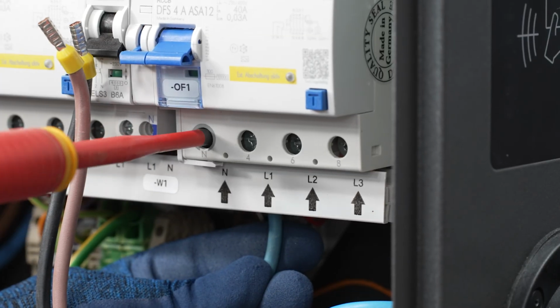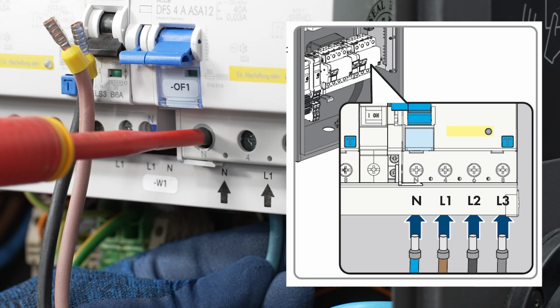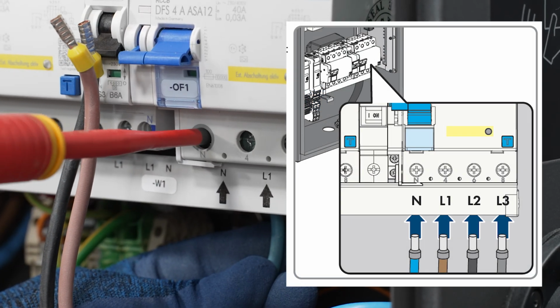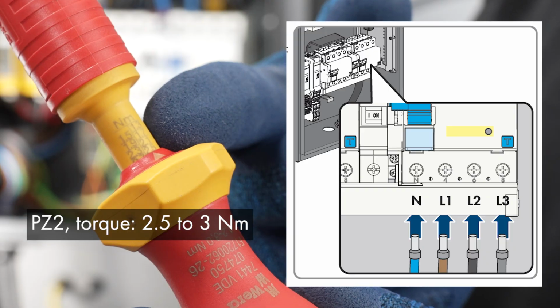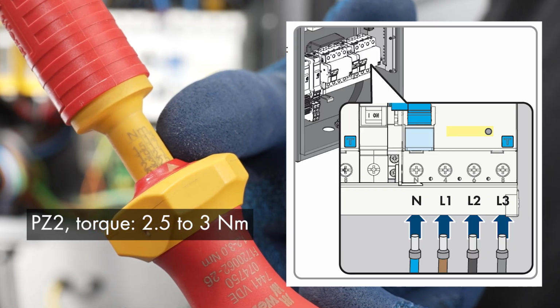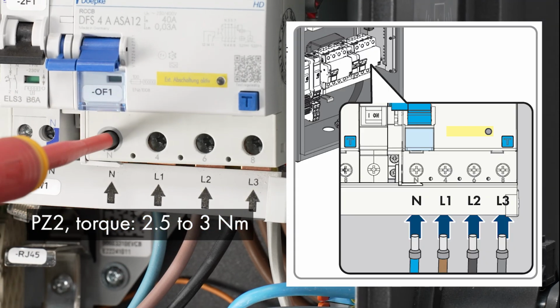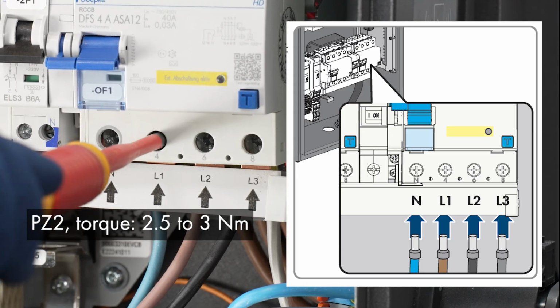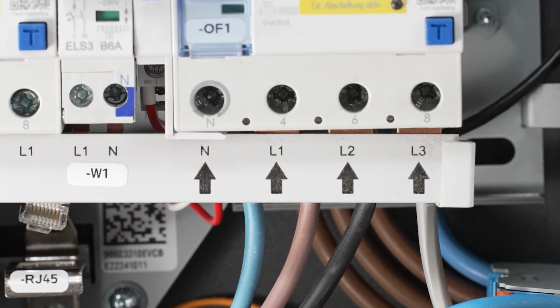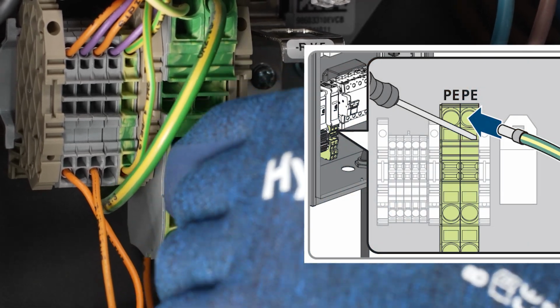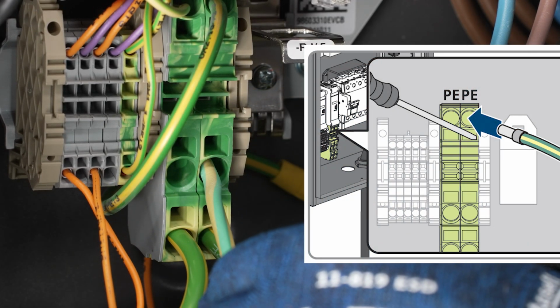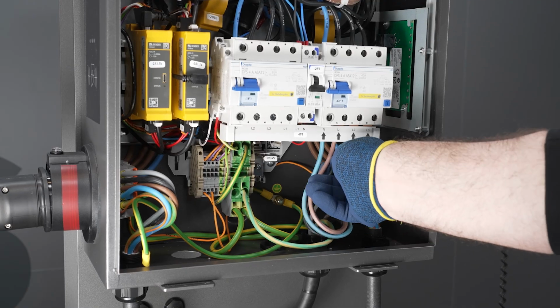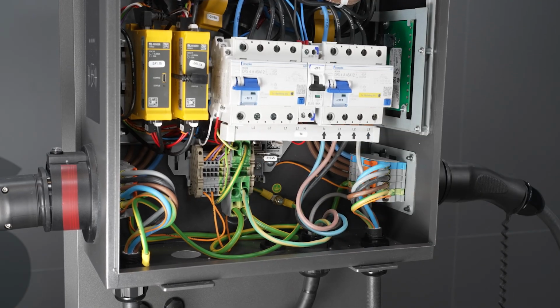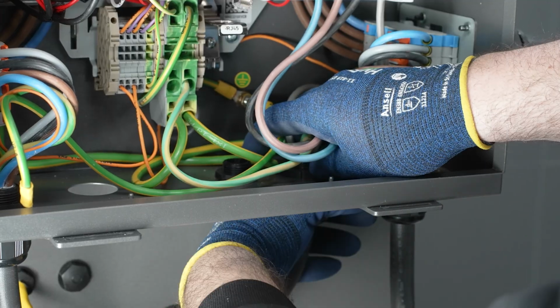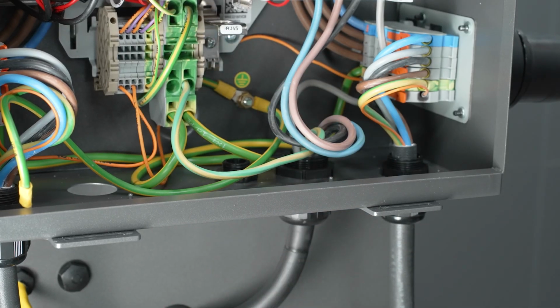Connect the conductors N, L1, L2, and L3 to the right residual current circuit breaker according to the labeling. Use PZ2 torque 2.5 to 3 Newton meters. Connect PE to the terminal strip according to the labeling. Ensure that all conductors are connected correctly. Tighten the union nut of the cable gland hand tight.